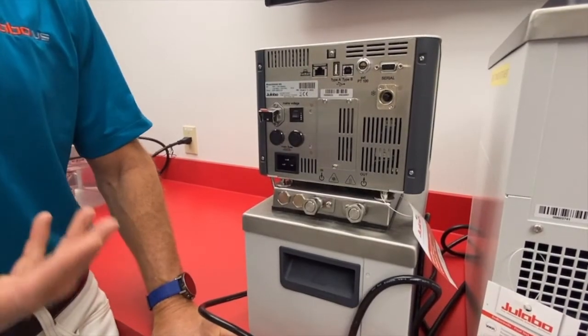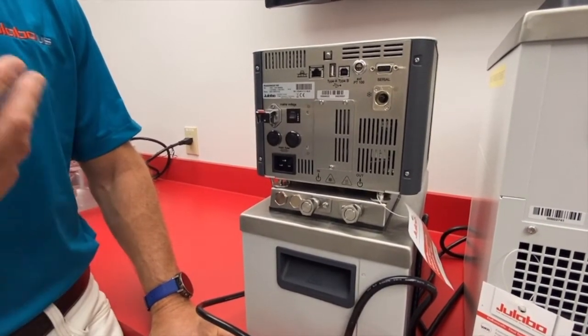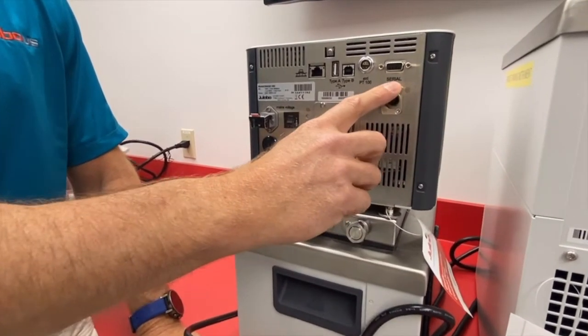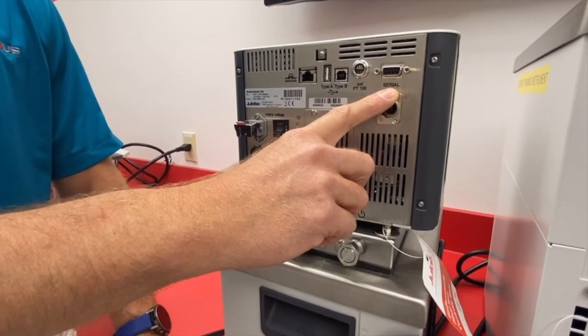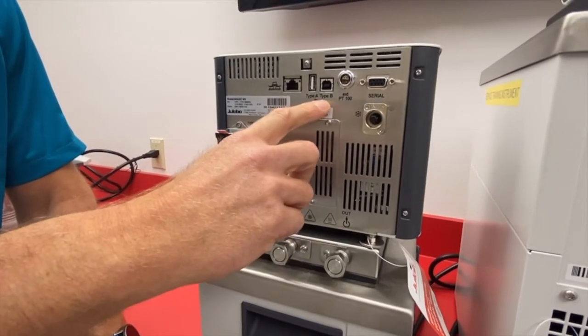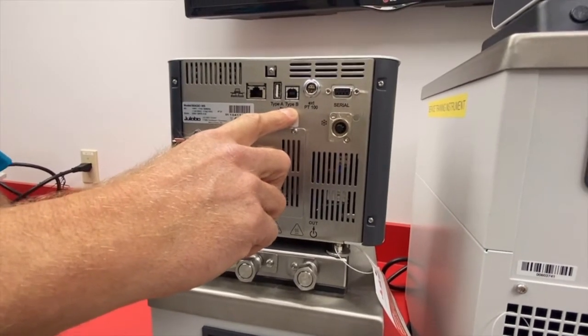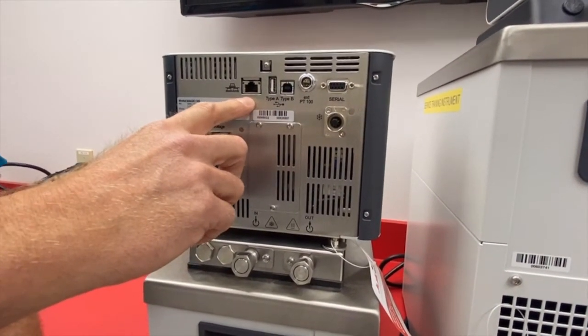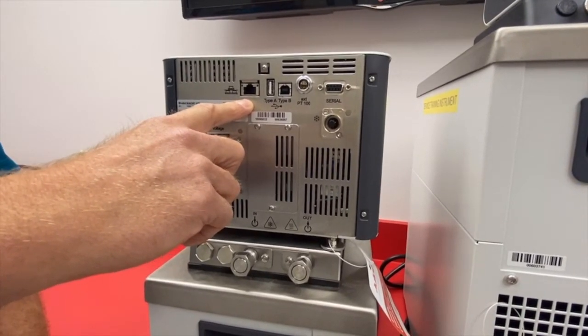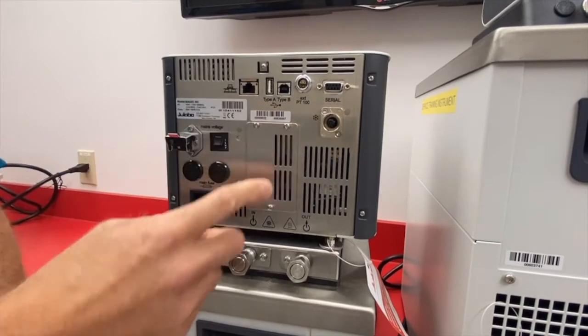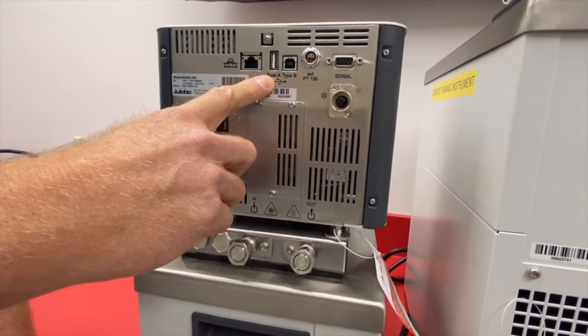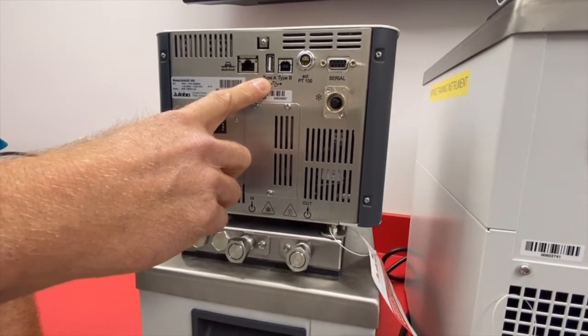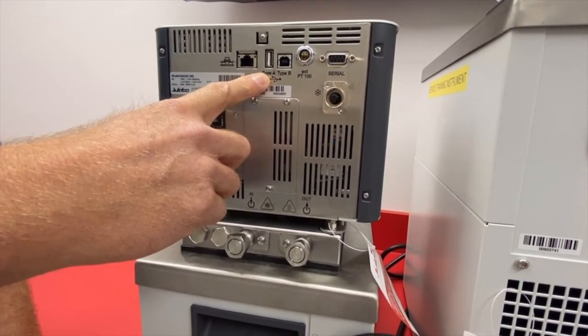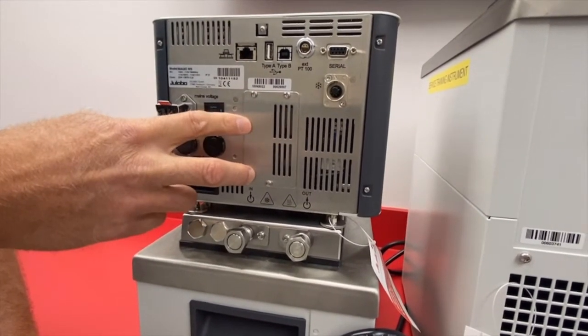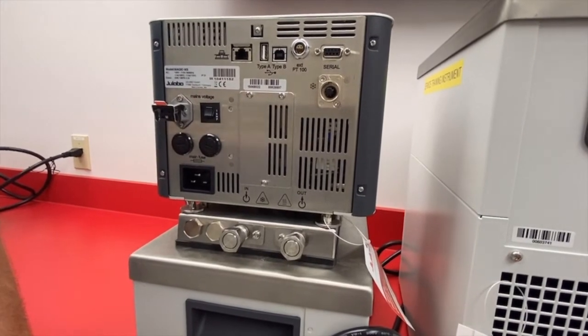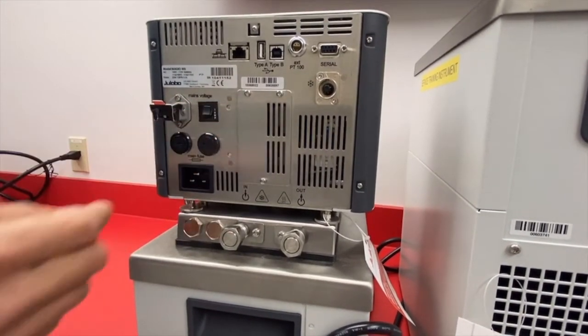In comparison, on the back of the MAGIO models, you can see there are a lot more options. From a communication perspective, we have a serial port, which can be used for RS-232 or RS-485 protocols, a USB type B port for USB communication, and an Ethernet port. The MAGIO also incorporates Modbus TCP/IP protocol. You have a type A port for data logging, but the MAGIO can also save programs that you can transfer from one unit to another. And then you have an optional slot here for analog. If your PLC requires communication via voltage or current, then you would use that module.